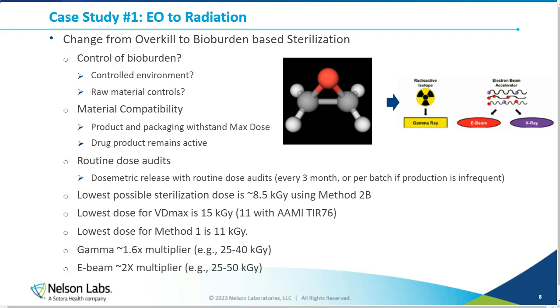For gamma, the general rule of thumb tends to be a 1.6 multiplier. An example of that is 25 to 40 kilogray. My product is going to see a minimum sterilization dose of 25 kilogray to be considered sterile, but it's potentially going to see upwards of 40 kilogray. For E-beam, a general trend is what is known as a 2x multiplier. So product is going to be dosed in a range of 25 to 50 kilogray. Now, these are generalities. Things are going to vary based on your irradiation provider, as well as your product and configuration, but that gives you a general idea of some of the ranges we're seeing for sterilization.